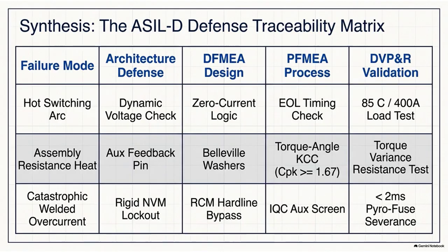They take those critical, heavy copper bus bar bolts and they deliberately over-torque them by 150%, actively risking thread shearing and fracturing the Belleville washers. Then they take other critical bolts and severely under-torque them by 50%, mathematically guaranteeing they are loose and will cause high impedance. They are intentionally building physical time bombs. They do this to rigorously prove the absolute efficacy of the factory's automated end-of-line testing stations.